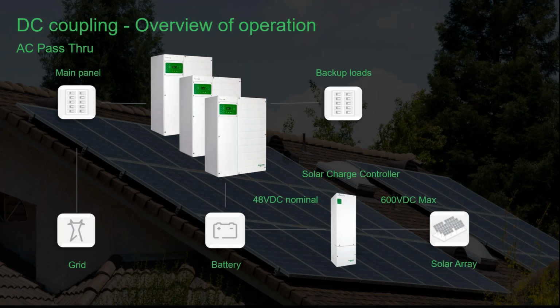Now let's have a look at a DC coupled configuration. Advantages to DC coupling are better efficiency when storing energy for use at a later time, and being able to monitor PV through our Insight platform. When in AC pass-through and grid power is present, the inverter charger will pass that power through directly to the AC appliances, and the PV power will charge the battery.